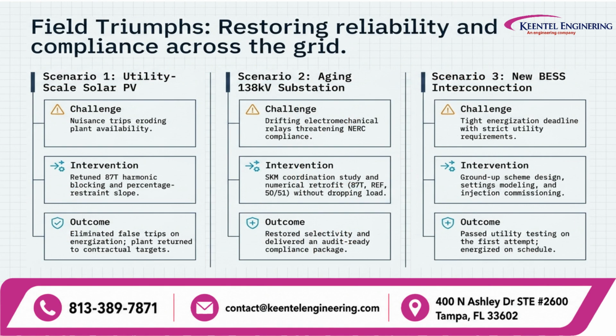The first scenario is utility-scale solar PV. The challenge was nuisance tripping that was reducing plant availability. The intervention involved retuning the 87T differential protection, including harmonic blocking and percentage restraint slope. The result was elimination of false trips during energization, allowing the plant to return to its contractual operating targets.